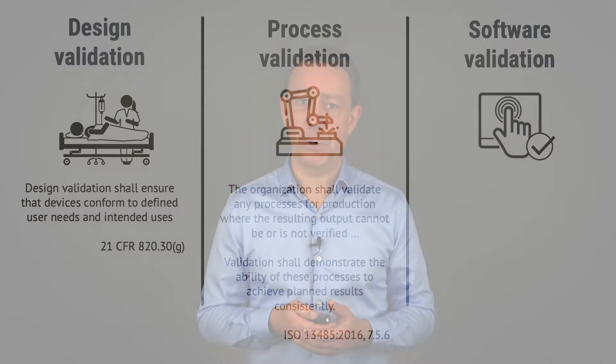Please note that if the test involves real human subjects that are patients, the design validation may qualify as a clinical investigation, which is a chapter on its own.